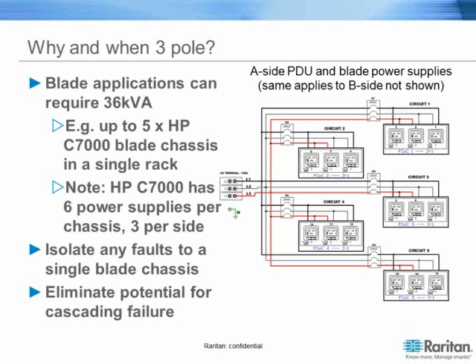Some customers want to have this out there. They want a no-fault data center. There's a way to ensure each plug, each C19, each blade power supply is protected by its own breaker. So that's up to the customer's choice of what they want to go with. We do specific double pole and triple pole breakers, but again, when utilizing this much power, we want to play it safe.